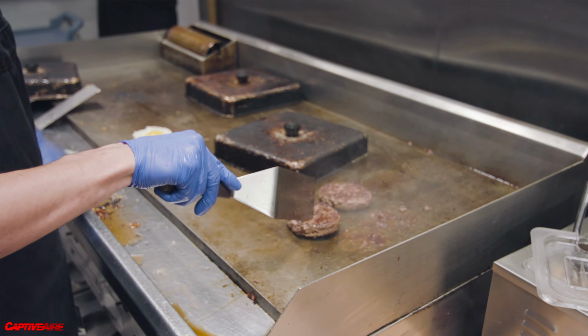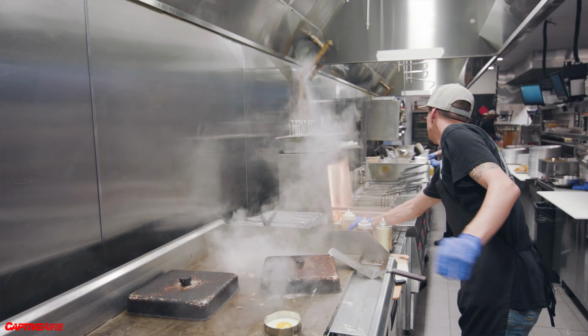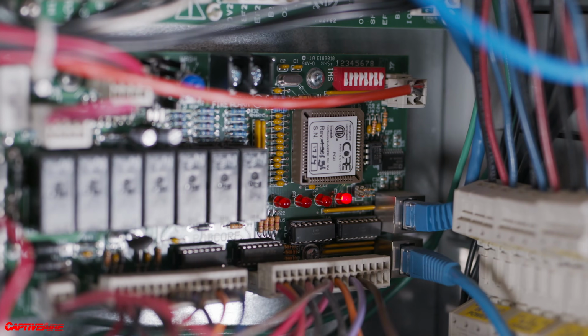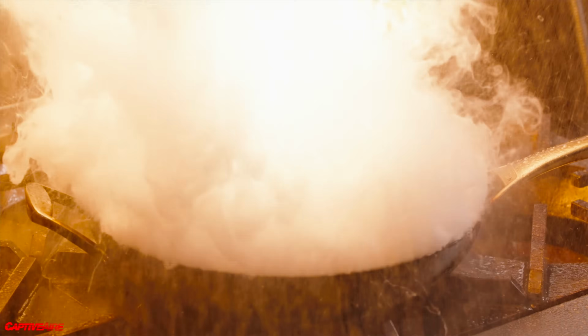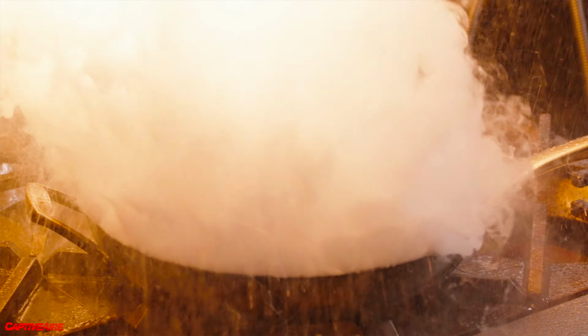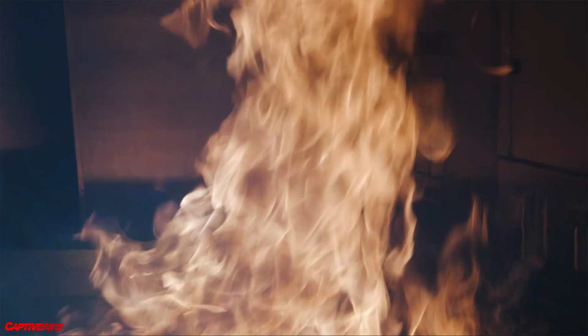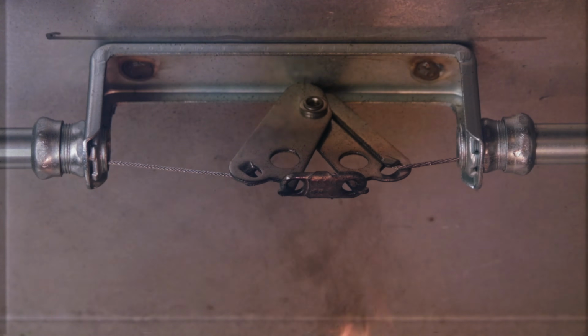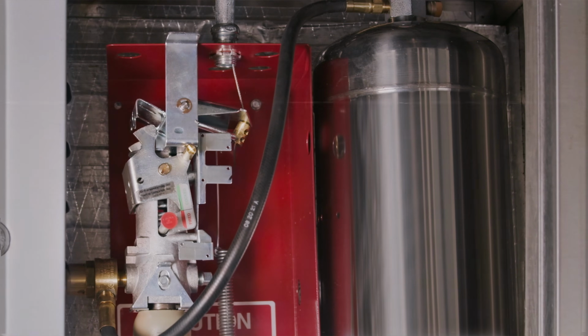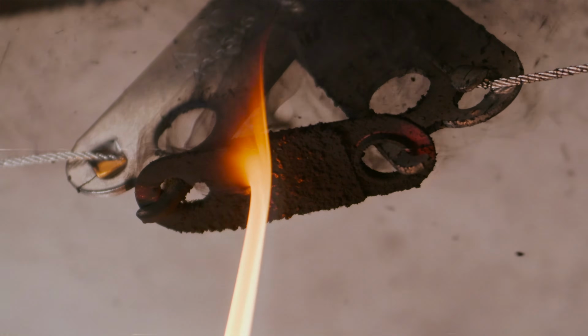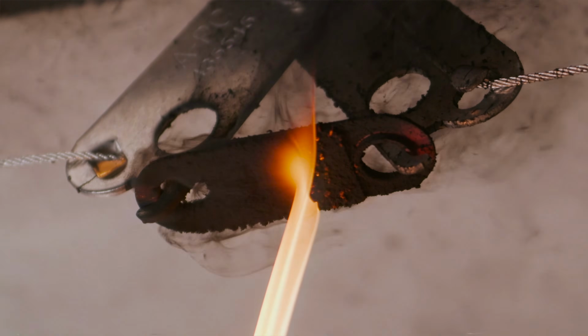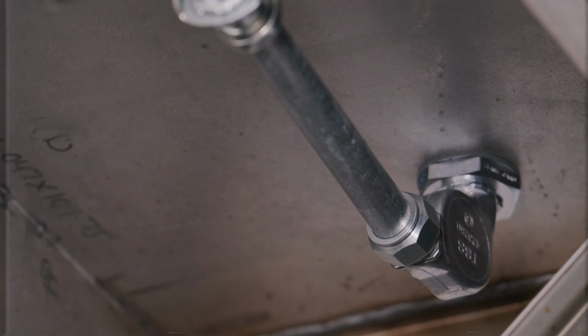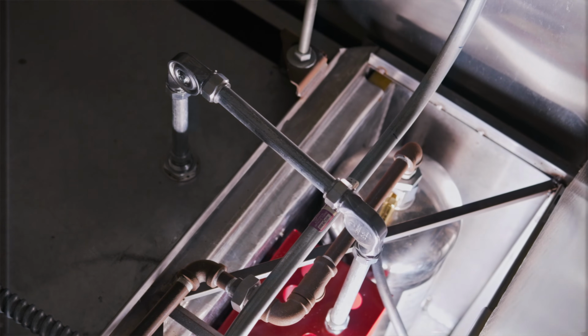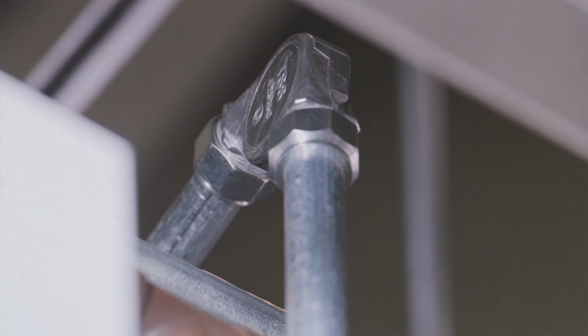The best way to avoid this scenario is to take that decision away from the person. Let the fire system decide if and when to activate. The legacy technology is mechanical detection to start. And that would be a fusible link that literally breaks upon a certain temperature, but they're very unreliable. Sometimes they will not fuse, or you have mechanical pulleys also that run through the system. Any one of those could fail, or they're not really detecting the fire that great in the first place.